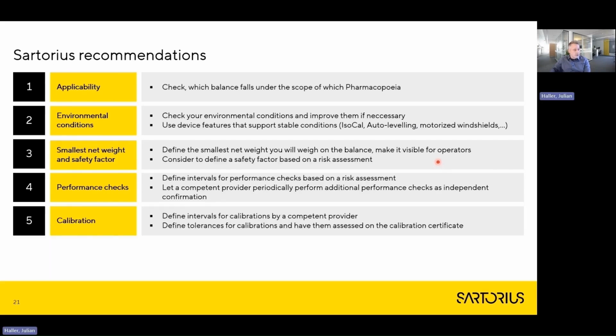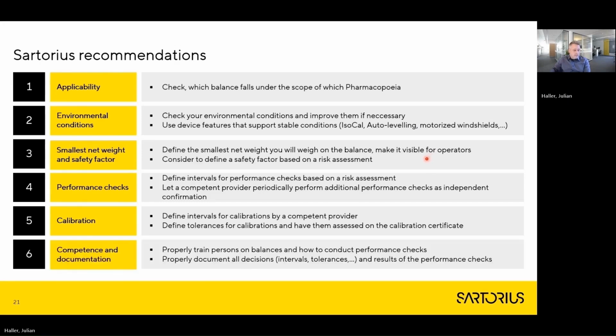Concerning calibration, we recommend to define intervals for calibrations by a competent provider and also to define tolerances for the calibrations and then either assess them on your own or, more convenient for the user, to have them assessed on the calibration certificate. Concerning competence and documentation, we recommend to properly train persons on balances and how to conduct performance checks, and to properly document all decisions like the determination of intervals and tolerances and the results of the performance checks.